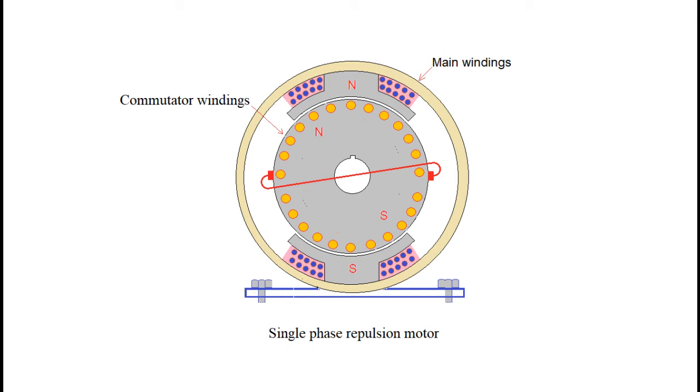Current that flows through this stator winding produces magnetic flux that pulsates between stator and rotor. The new feature of this motor is it has distributed winding on rotor side that closes on itself through commutator to form a closed path. This winding arrangement is identical with that of DC motor, only difference is field windings are supplied through AC supply. As it is known from DC motor's commutator winding that coils of windings are full pitch coils, and these coils connect with successive coils through commutator segments.